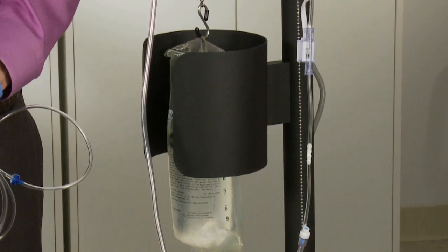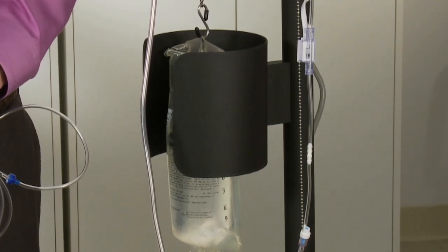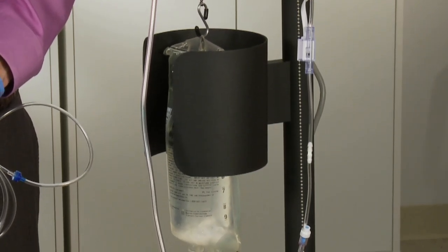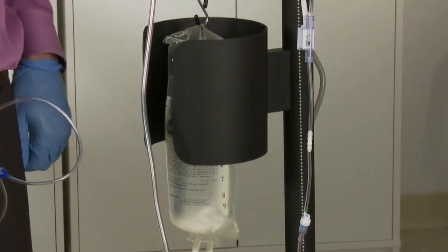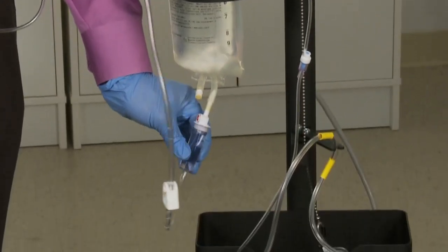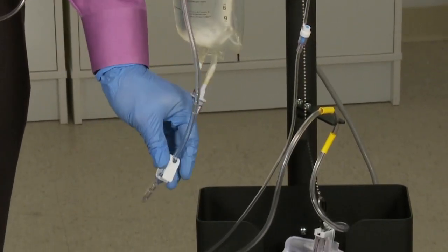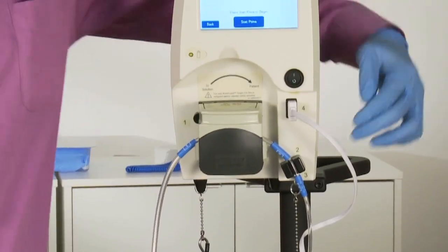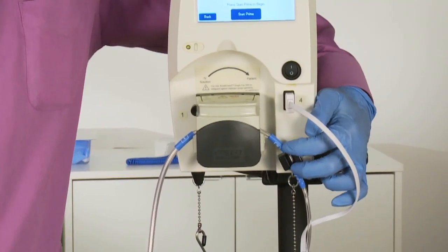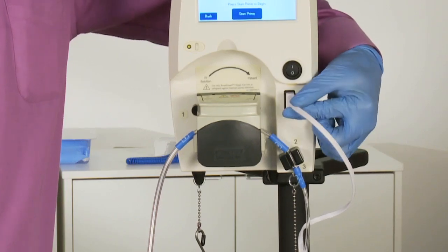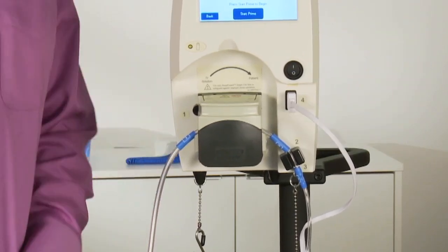Okay, let's make sure everything is installed correctly one more time before we continue. The infusion bag is hanging freely, our drip chamber is filled, and the clamp on the infusion line is open. The line is installed in the pump. Our 1, 2, 3 are lined up. The tubing is in the air detector, and our pressure sensor is connected.